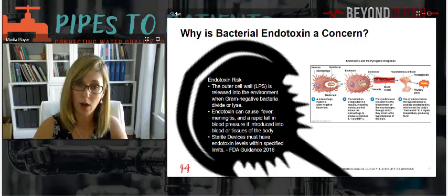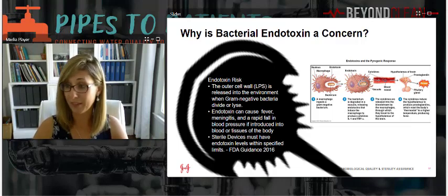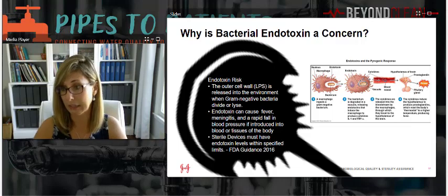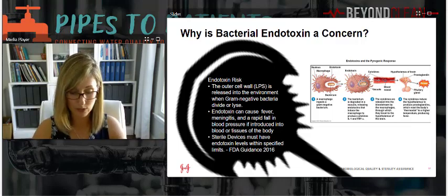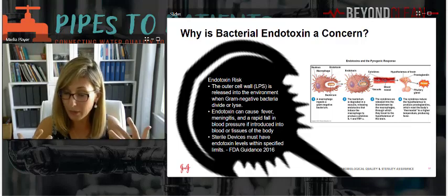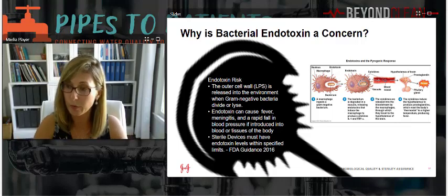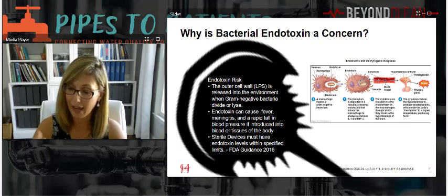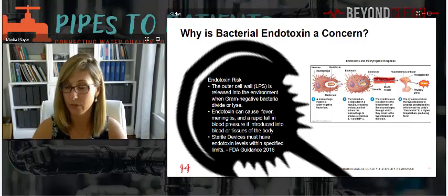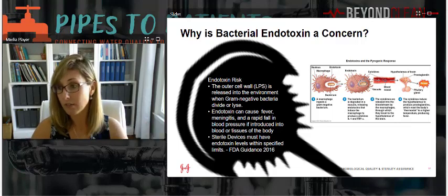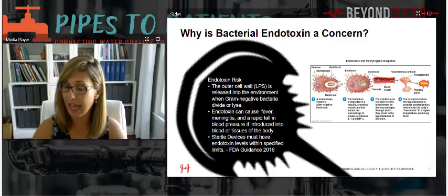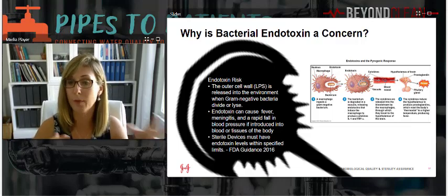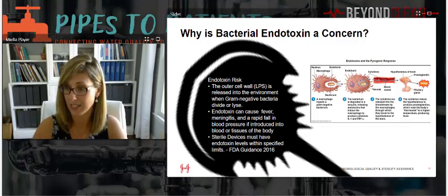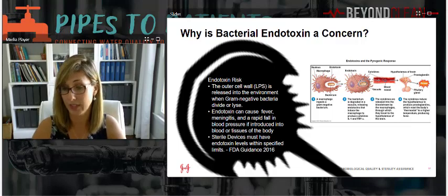If you're not controlling your water system, maybe you want to think about using sterile single-use implants, because remember, we use sets where implants, although not clinically used, are still reprocessed over and over again. Think about screws and other orthopedic set pieces that stay in the set and get recycled repeatedly, but never come in contact with the patient. They still carry that patient safety risk if you're worried about bacterial endotoxin depositing on it and not being removed during processing.